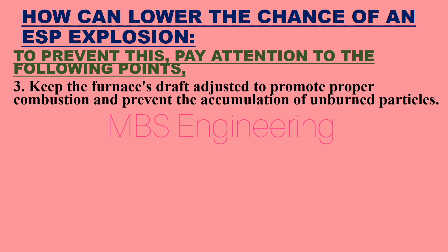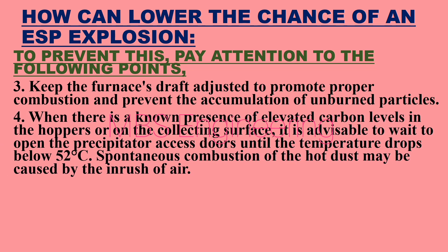Point 3: Keep the furnace draft adjusted to promote proper combustion and prevent the accumulation of unburned particles. Point 4: When there is a known presence of elevated carbon levels in the hoppers or on the collecting surface, it is advisable to wait to open the precipitator access doors until the temperature drops below 52°C. Spontaneous combustion of the hot dust may be caused by the inrush of air.